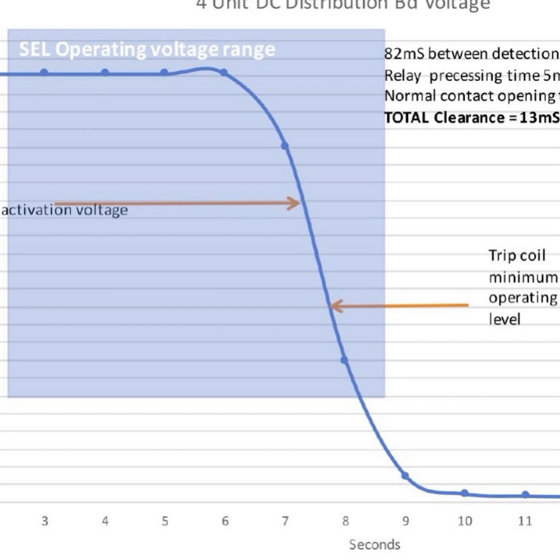Not having a copy of the procedure, I can't be sure there wasn't a call out to use the manual changeover switch under a failure scenario, but the fact it wasn't suggests it wasn't considered. Maybe that's being too nitpicky, but when you're working on critical systems, the more you pre-plan and pre-assess, the less likely you are to have issues recovering when you're in the moment, under intense pressure to make the right decision.